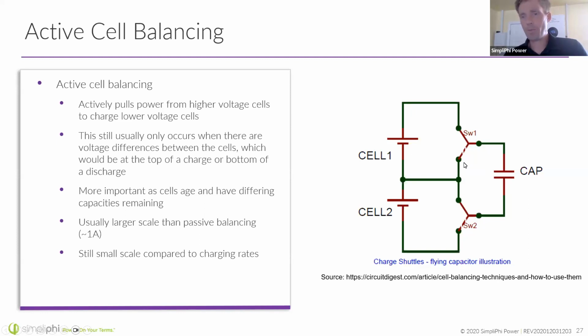If these switches flip into the downward position, that same capacitor, which had charged up off cell number 1, would now be in parallel with cell number 2. And so with the switches in the downward position, the capacitor would discharge, if cell number 1 was at a higher voltage, into cell number 2. This is the more sophisticated and much more efficient way to charge battery cells up. And this is the type of cell balancing that we use through our BMSs.